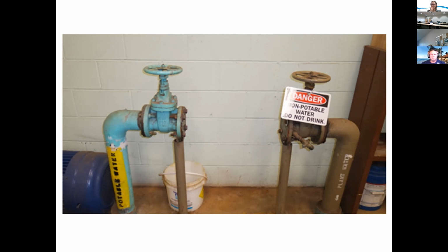And you start thinking, well, wait a minute, if they can just spin 8 bolts and reinstall that backflow assembly, what are the odds of them doing it in the future? And you need to remember your definition of actual or potential cross connections with the potable water system. And I guarantee that backflow assembly sitting on the floor over there hadn't been tested in 10 years.